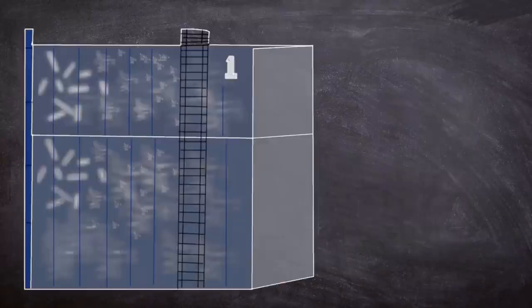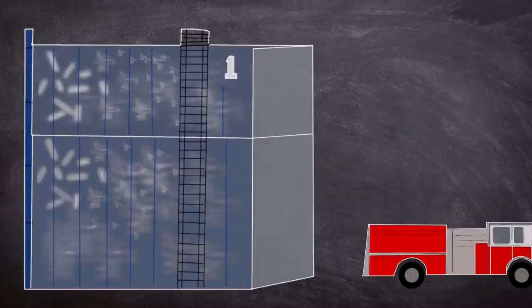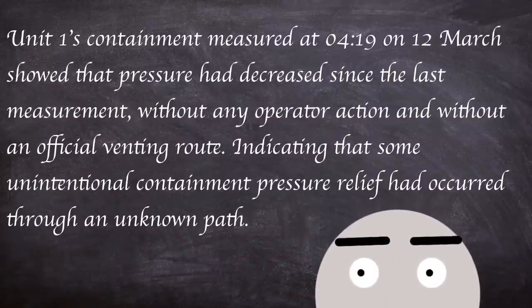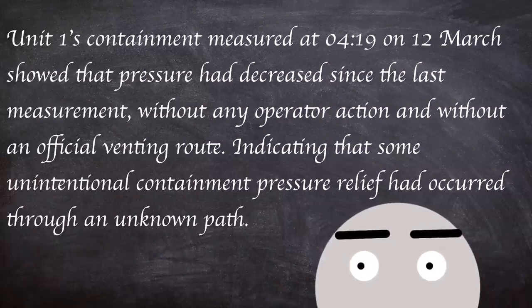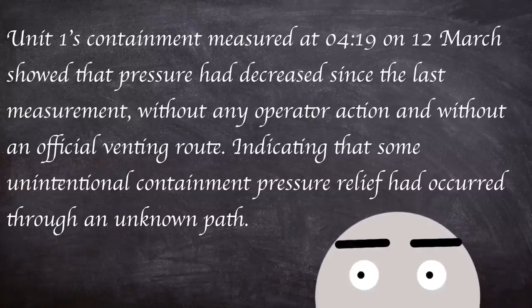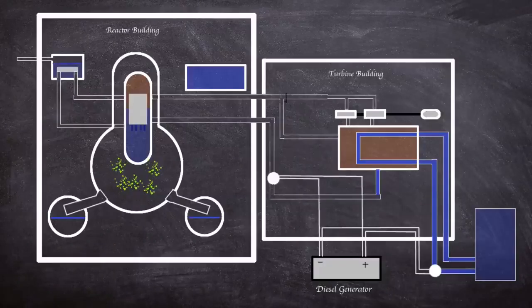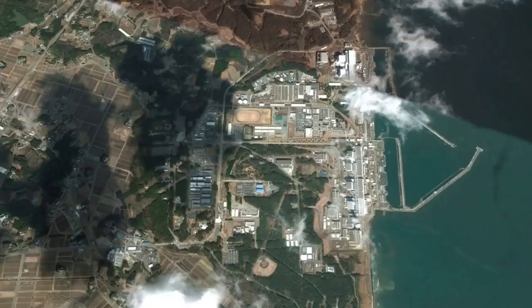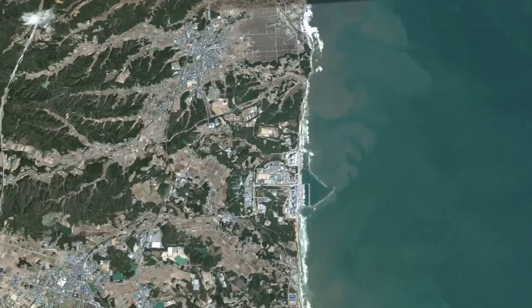At 4 am an alternate cooling system was put into operation using fire trucks pumping seawater into unit one as the vessel pressure had reduced. Unit one's containment measurement at 4 19 am on the 12th of march showed that pressure had decreased since the last measurement without any operator action and without an official venting route indicating that some unintentional containment pressure relief had occurred through an unknown path. This coupled with an increase in radiation levels hinted at reactor vessel damage. Because of this the government extended the evacuation zone to 10 kilometers.